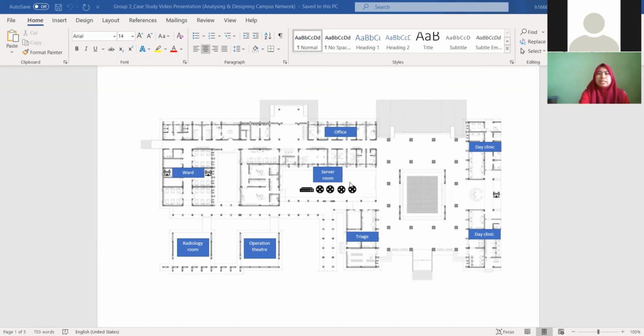Next, the location must be suitable for the installation of bulky power, air conditioning, and networking equipment. It must be able to bear the weight of heavy IT equipment when you build a server rack. Then, tight spaces are not suitable because effective cooling requires the constant circulation of air and proper airflow planning. It's also inadvisable to build a server room in a window space or a space with an external wall, both of which can make it difficult to control and secure the environment within the server room. Okay, that's all from me.